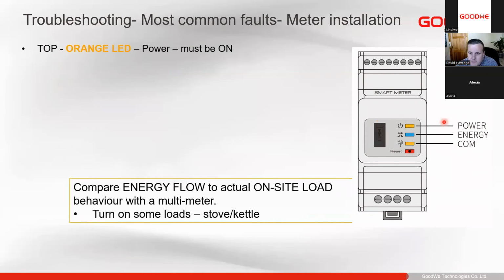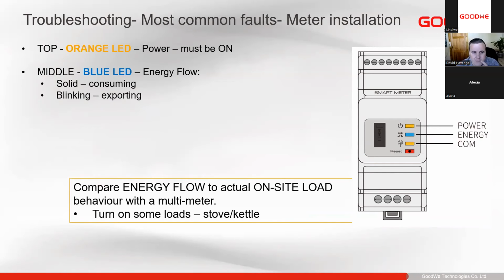So next, the smart meter. Especially for the on-grid, so if you're installing a smart meter just to power control one single on-grid inverter, you have to use the LEDs on the smart meter to make sure whether that's correct or not. So obviously the top one must be on, which means it's powered on. Blue is the energy flow. So if it's solid, we're consuming from the utility. So we should see solid when there's just a smart meter connected and no inverter. We should see that LED is solid. If it is flashing, it means we are exporting. So if you only have the smart meter powered on and you see it flashing, then there's definitely a wiring mistake on the smart meter.